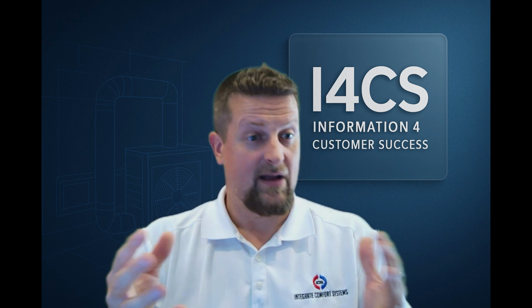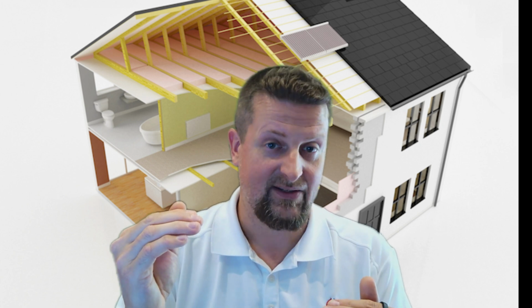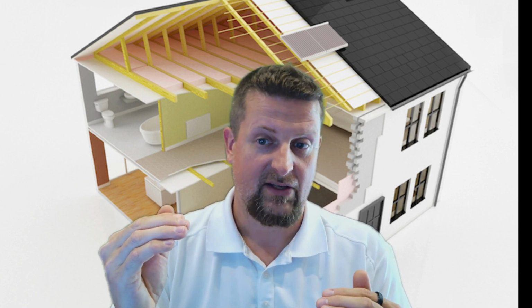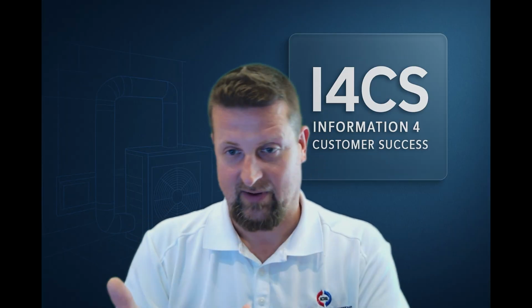So on a hot day, when your AC turns off, how fast does the house start to heat up? There's houses where literally once the AC turns off, you just feel the heat beaming from every direction. And in 5 more minutes, the AC turns back on because the temperature went up already so much. So that's a poorly insulated house. And then if you have a very well insulated house, well, it could be that it could take hours for a degree to even rise after your AC turned off. So is it an AC problem or is it a house problem? In situations like this, essentially it is a little bit of a house problem.